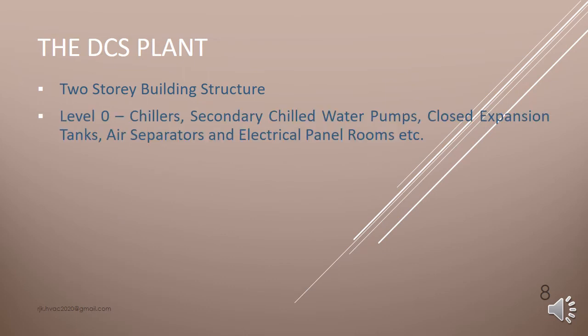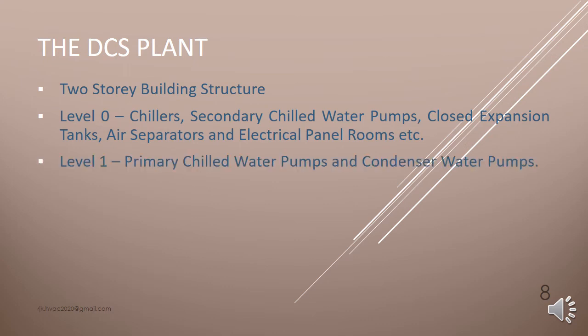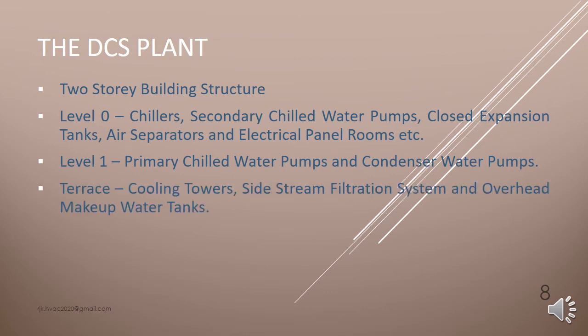The DCS plant. The DCS plant can be a two-story building structure. At level 0, we can have chillers, secondary chill water pumps, closed expansion tanks, air separators, and electrical rooms, etc. At level 1, we can have primary chill water pumps and condenser water pumps. At terrace, we can have cooling towers, side stream filtration system, and overhead makeup water tanks. The thermal storage tanks will be located outside the building.